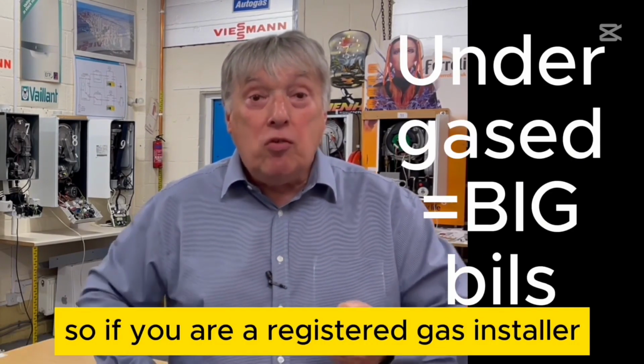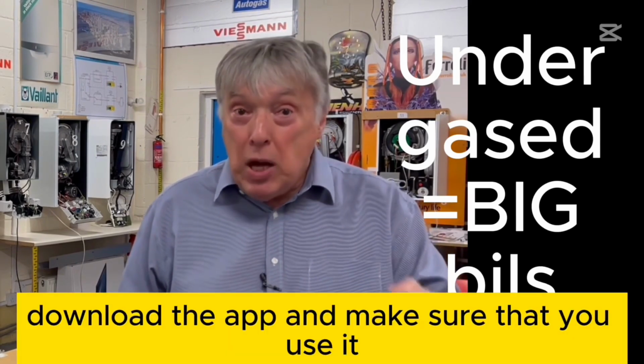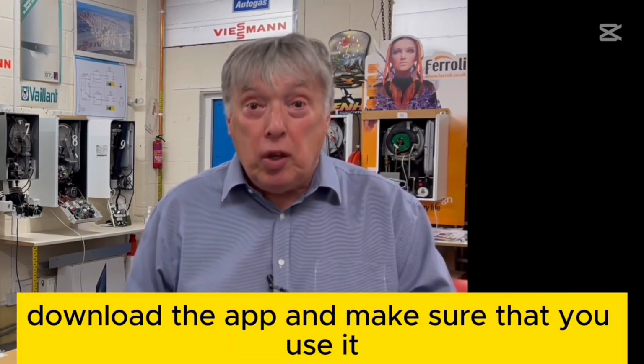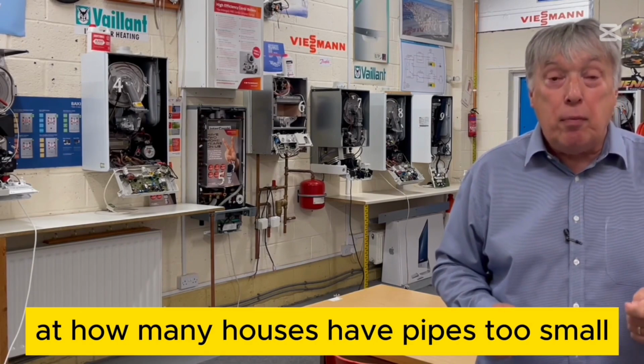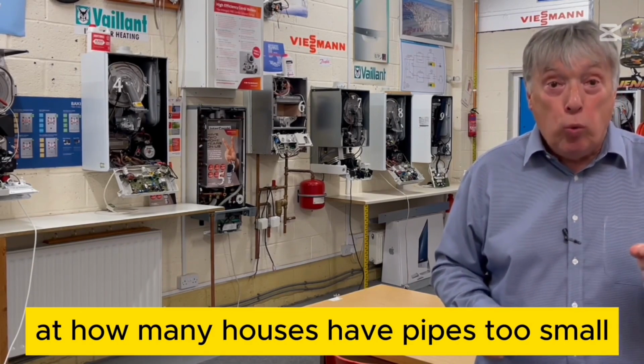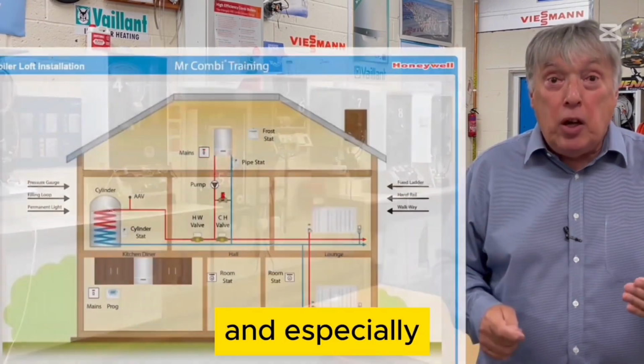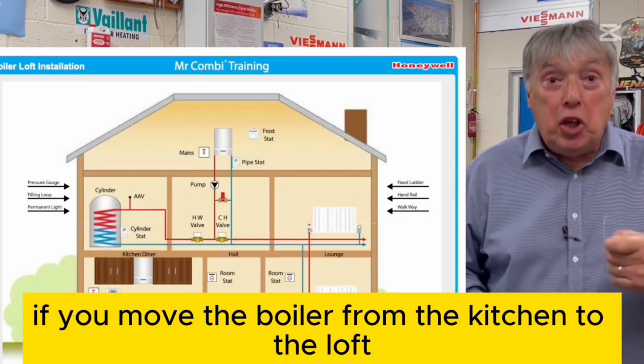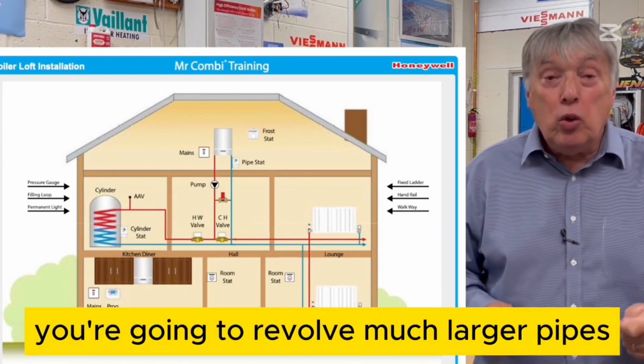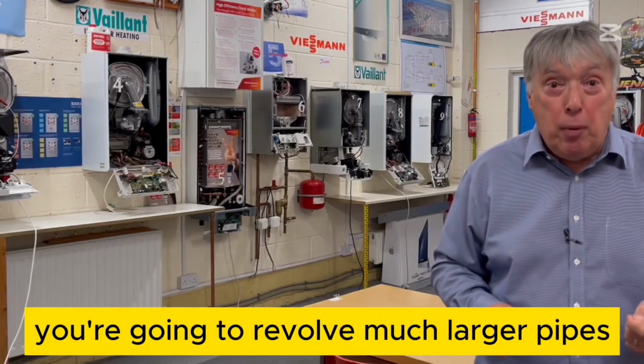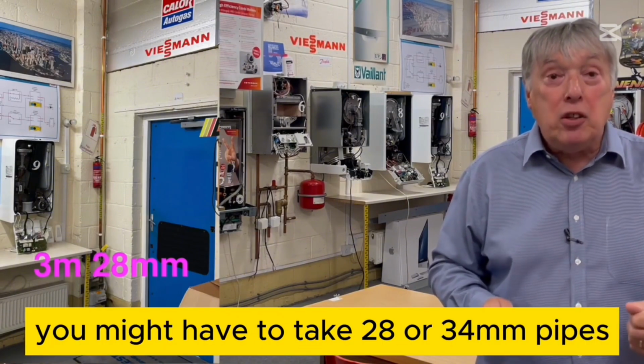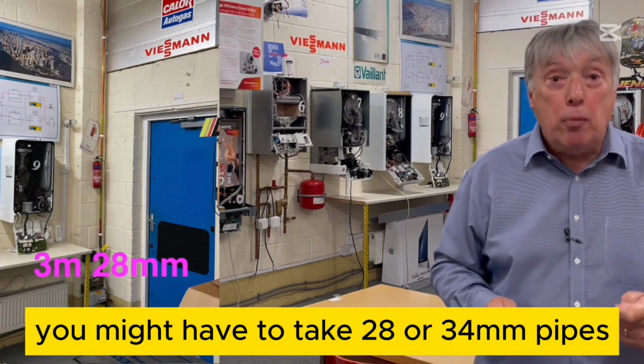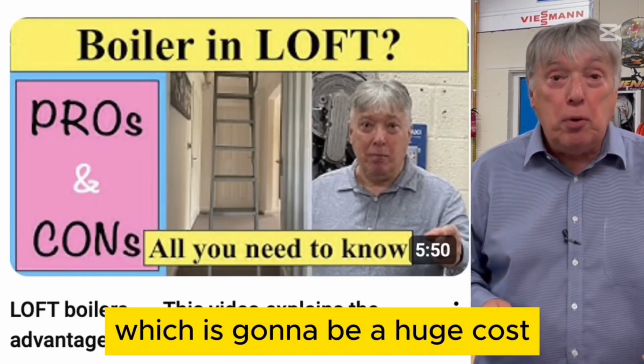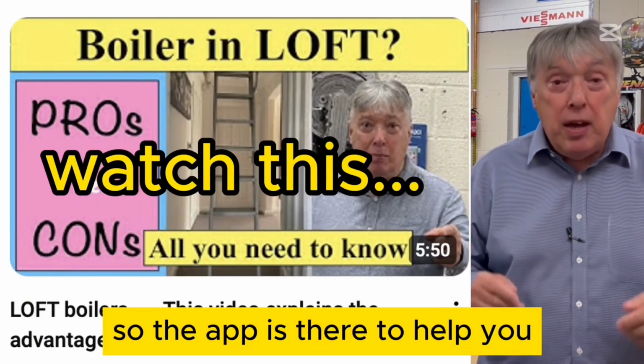So if you are a registered gas installer, download the app and make sure that you use it, because you'll be surprised at how many houses have pipes too small and we need to update them. And especially if you move the boiler from the kitchen to the loft, you're going to require much larger pipes. Forget 22mm, you might have to take 28 or 34mm pipes all the way up to the loft, which is going to be a huge cost. So the app is there to help you make sure that you get the correct size.